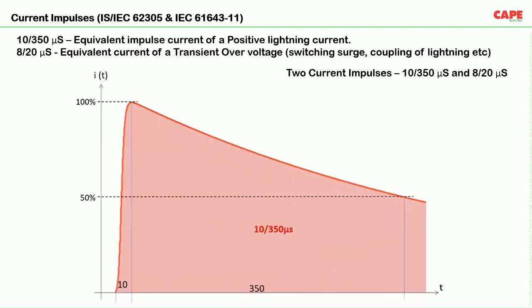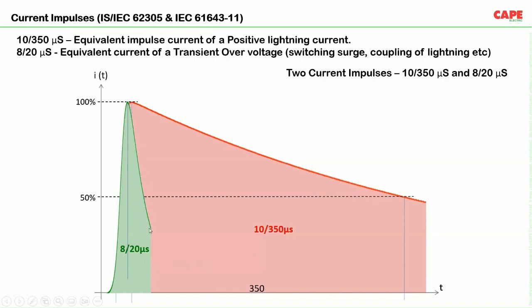Looking at the graph: the 10/350 microsecond impulse goes from 0 to 100% of its peak value in 10 microseconds, and from 100% to 50% of its peak value in 350 microseconds — hence it is called the 10/350 waveform. Similarly, the 8/20 waveform reaches its peak in 8 microseconds and decays to half its peak in 20 microseconds. The lightning impulse has very high specific energy and charge, so it creates more damage than an 8/20 microsecond impulse.